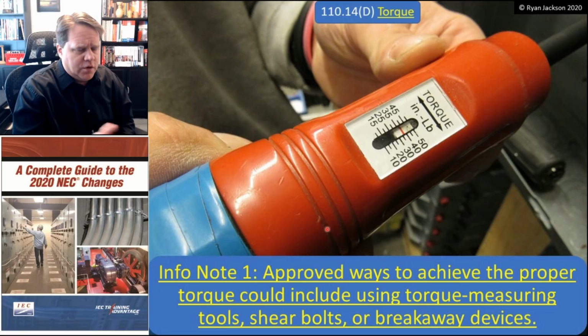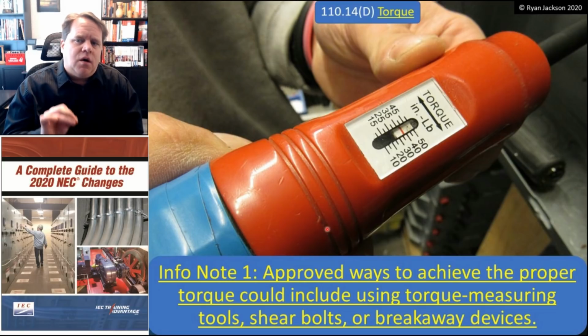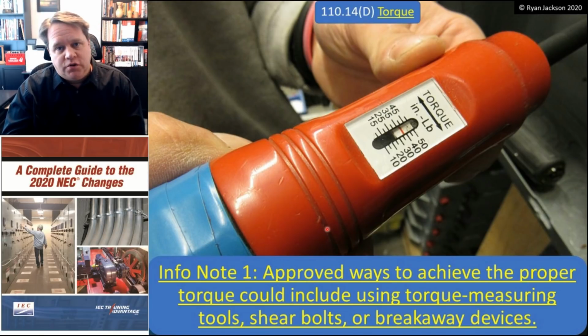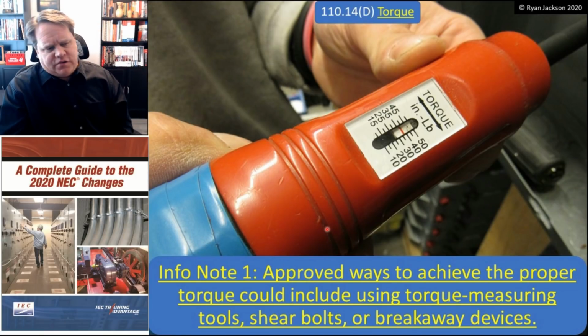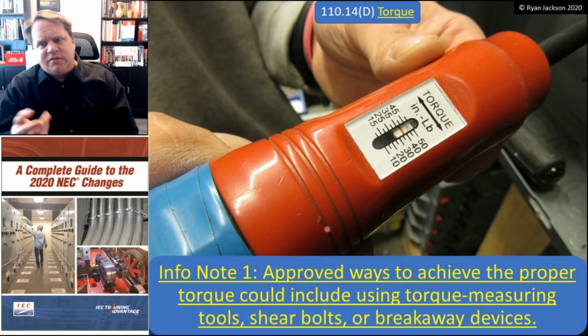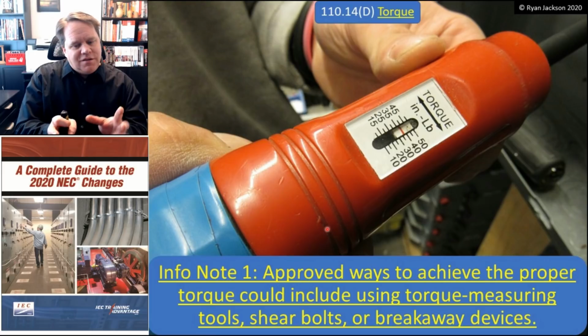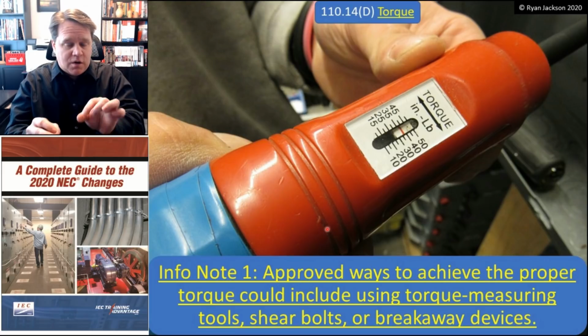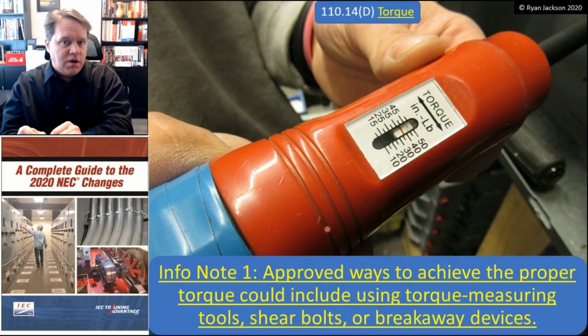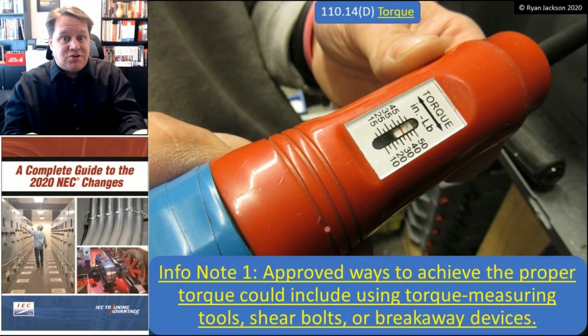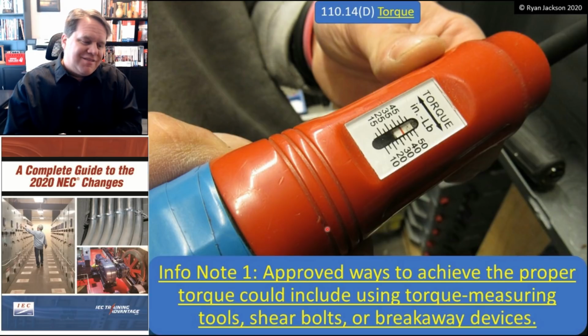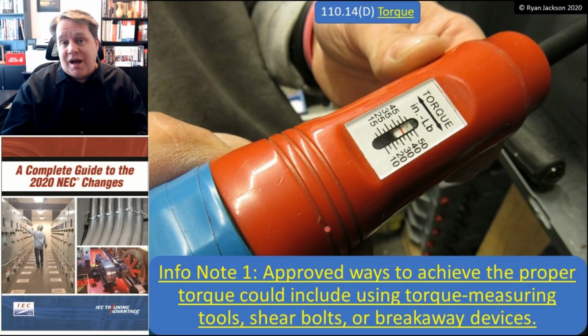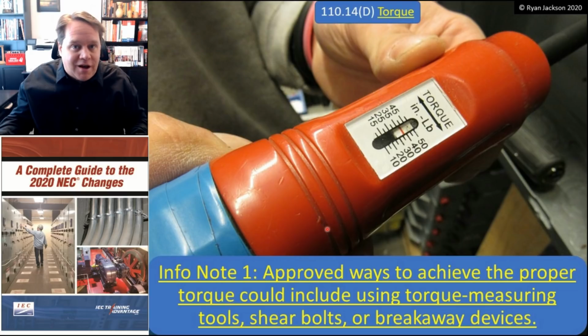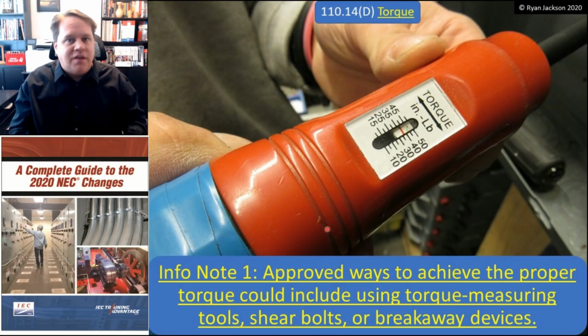Now, previous versions of the code in 2017 said you have to tighten it down and use a properly calibrated torque measuring tool. And that was revised for a couple of reasons in the 2020. First of all, when you read it, you tend to focus on the properly calibrated tool part instead of the rule itself that says, hey, make sure you're doing it right. Plus, do we really need to say that the tool has to be properly calibrated? That kind of goes without saying, doesn't it? You don't measure things with improperly calibrated measuring devices. I don't think we need to talk about that. That's pretty obvious. So, of course, it needs to be properly calibrated.